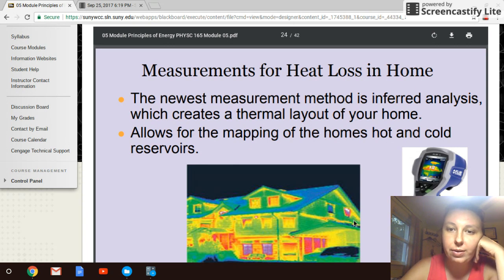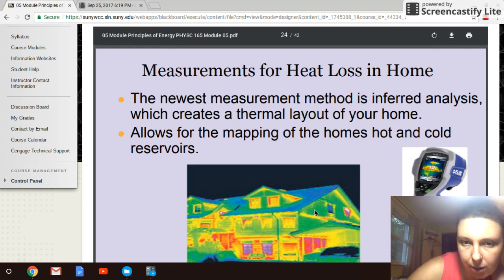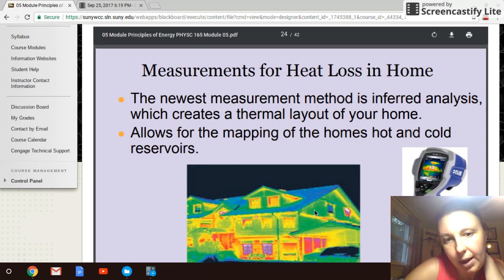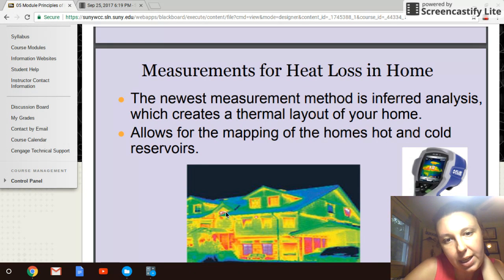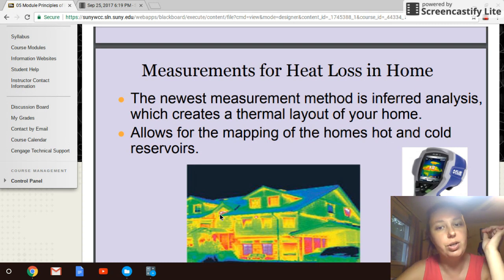But this one here is an interface change. That's because there's no insulation between the interface change of the roofing and the siding, and so the heat is just sliding right through. Sometimes where we see it, it's not that there's a heat exchange, but there's actually damage, or there's no insulation at all, and that has potential in this spot right here. So that's an interface change where the roofing's coming down, but it could also be damage, and it could be water damage, which is another interesting thing that I'll point out.